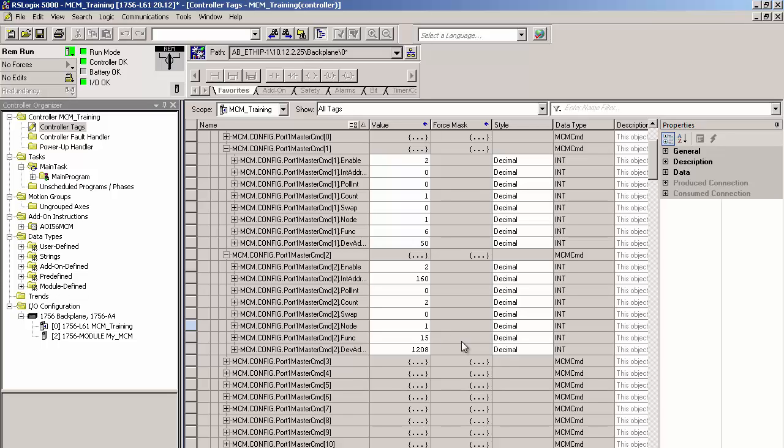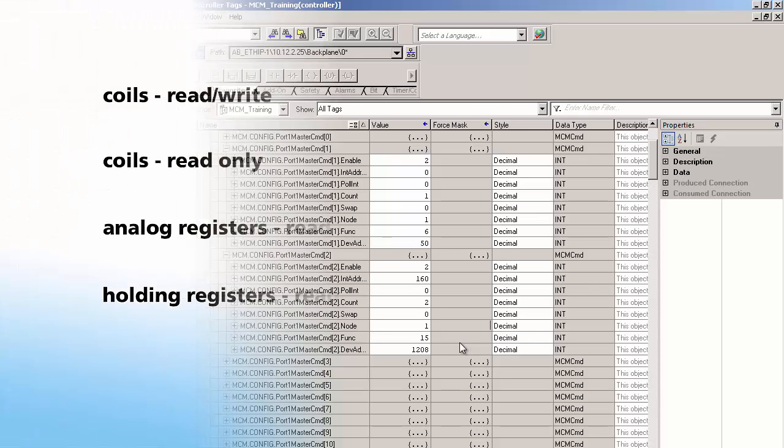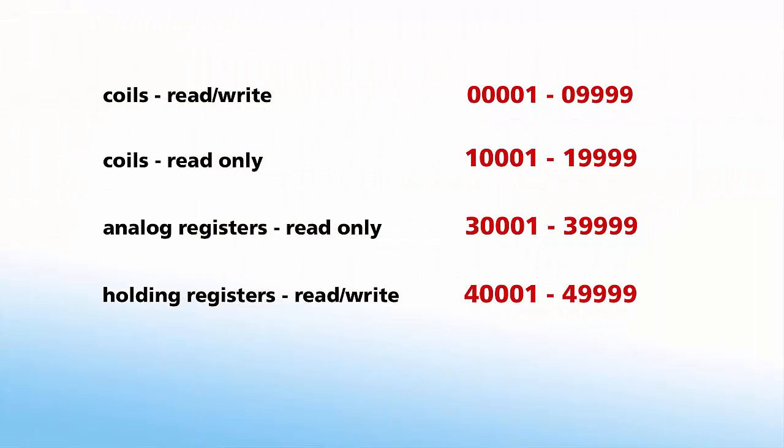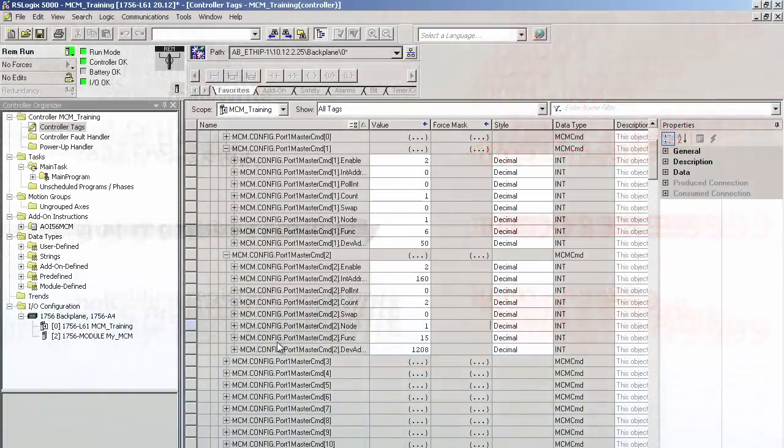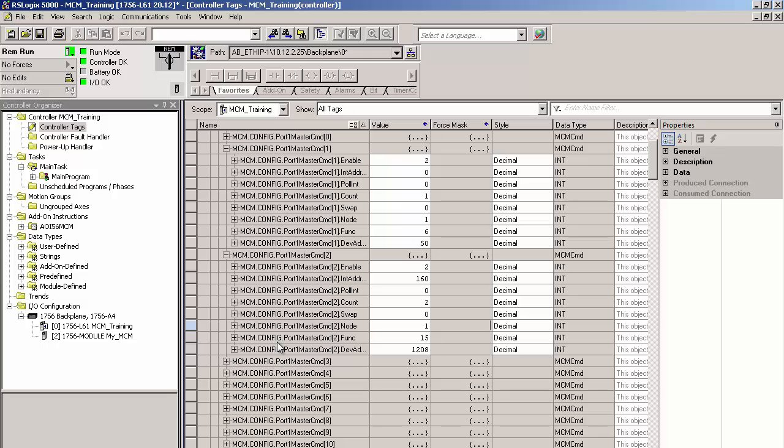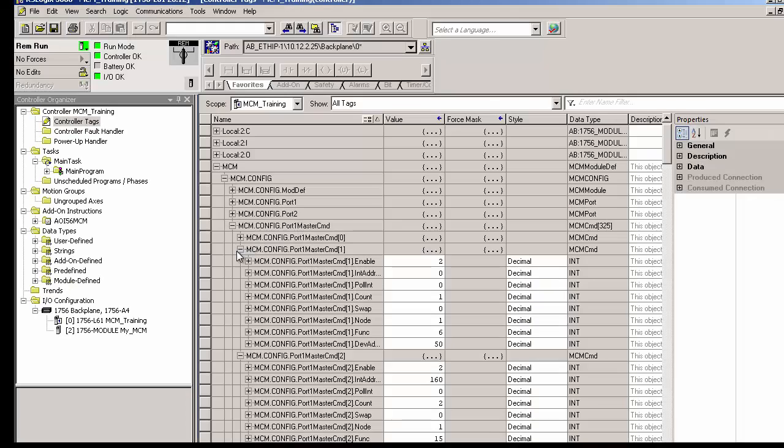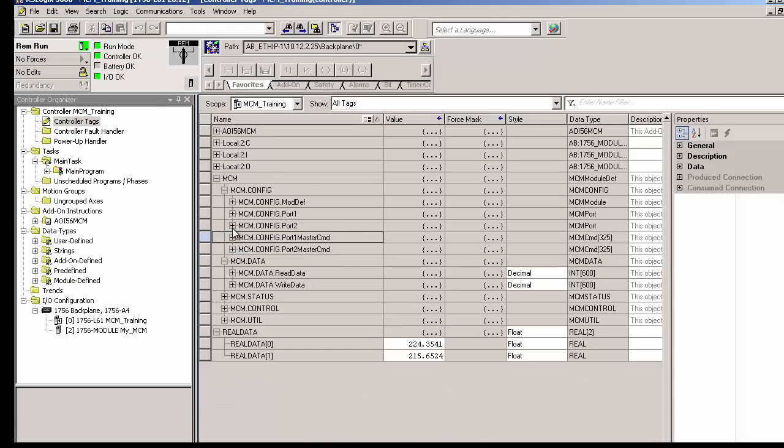Now, you should know that there are devices that will place the bits to enable and disable functions not in the bit level address range, but in the regular 16-bit holding registers in the 400001 address range. If you find you need to read or write bits in that range, you won't use a bit level function code. You'd use a function code to read or write to the register where the bits you want are situated. Now that my commands are set up, I'll warm boot the module.